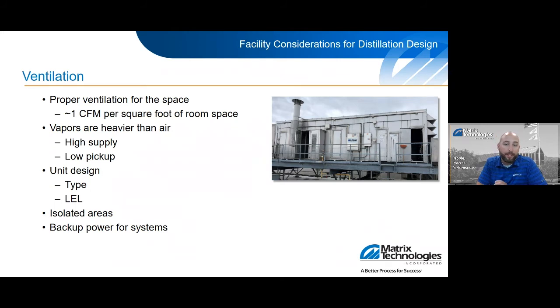A recirculated system with fresh air makeup can be installed. Just make sure when you choose this, you can have gas, steam, or electric, but you need to be sure that you're not in direct contact with the flame because you may have some vapors in that airstream that you don't want to ignite. But regardless of the type of unit that you select, it's key that you have LEL detection, or low explosive limit detection, in the system.